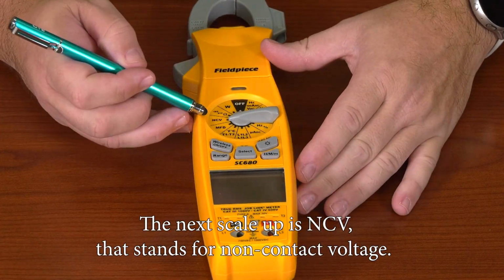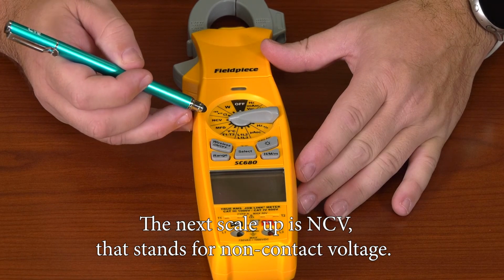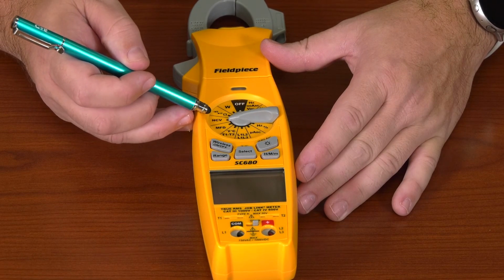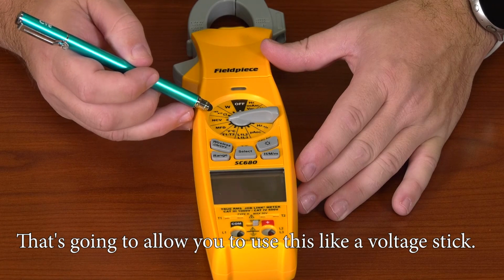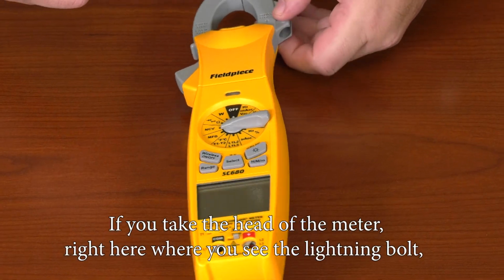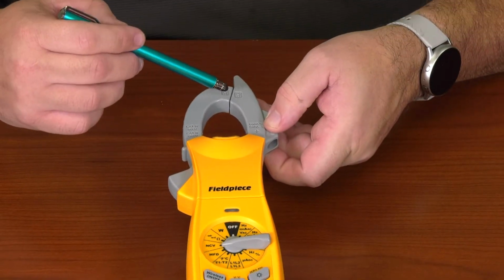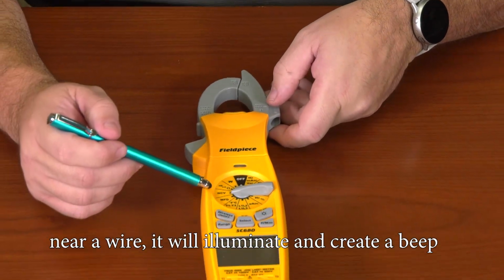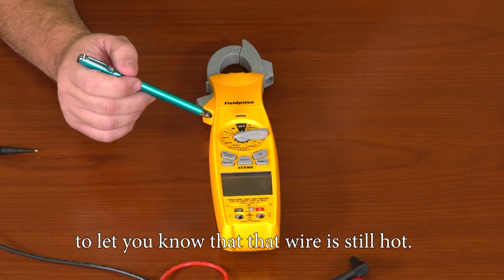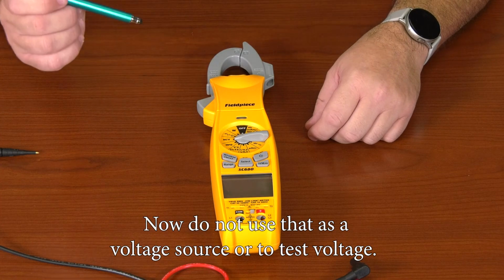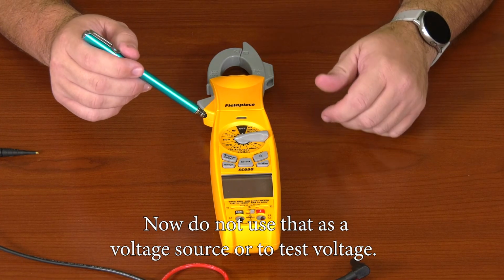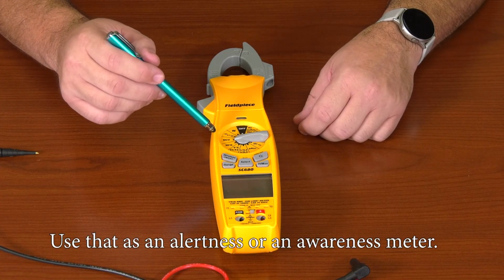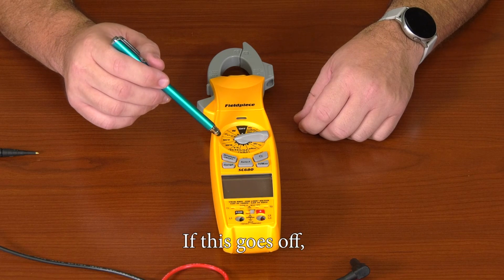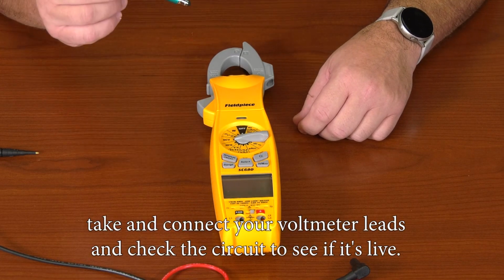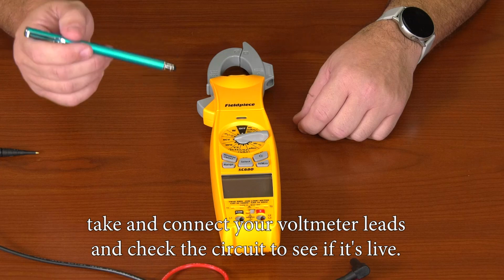The next scale up is NCV. This stands for non-contact voltage. That's going to allow you to use this like a voltage stick. If you take the head of the meter, right here where you see the lightning bolts, near a wire, it will illuminate and create a beep to let you know that that wire is still hot. Now, do not use that as a voltage source or to test voltage. Use that as an alertness or an awareness meter. If this goes off, take and connect your voltmeter leads and check the circuit to see if it's live.